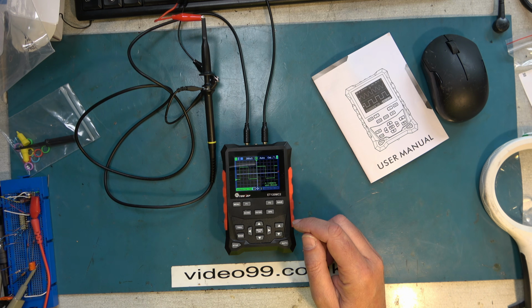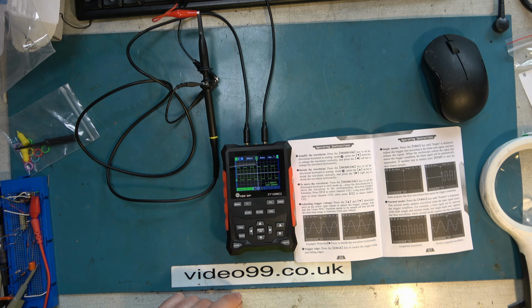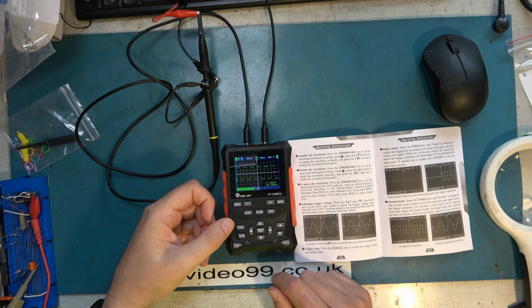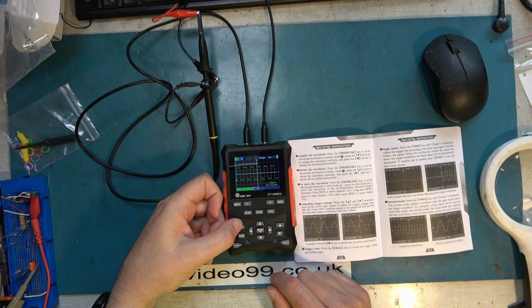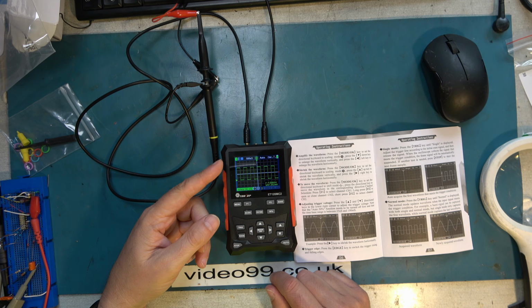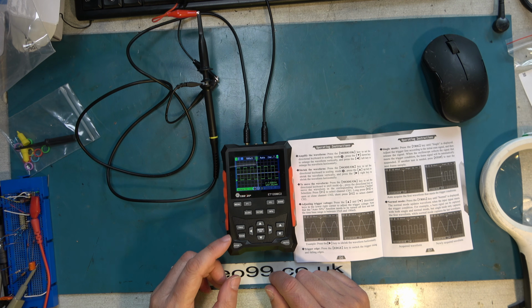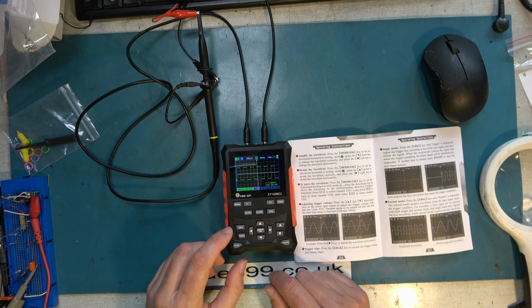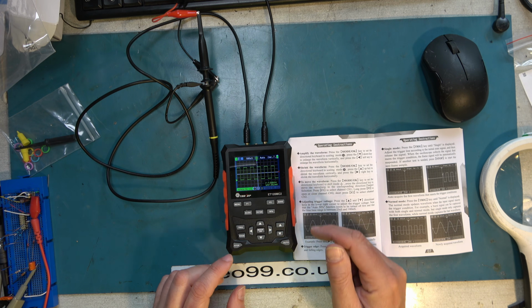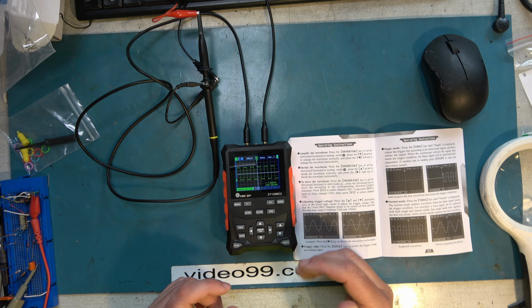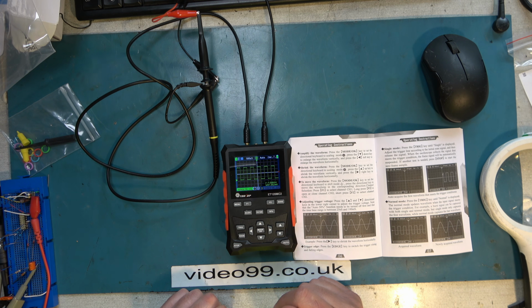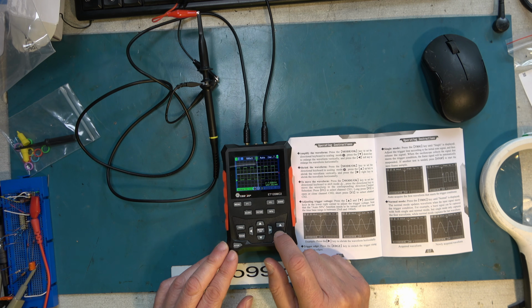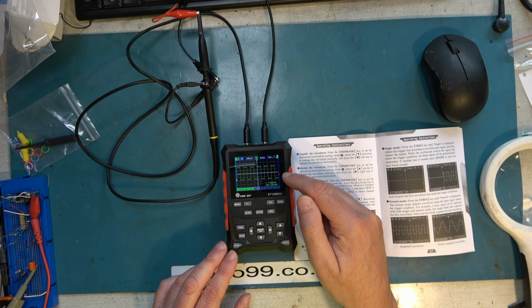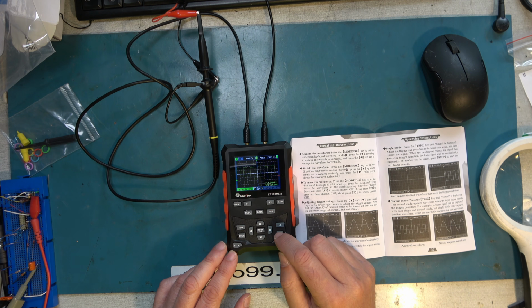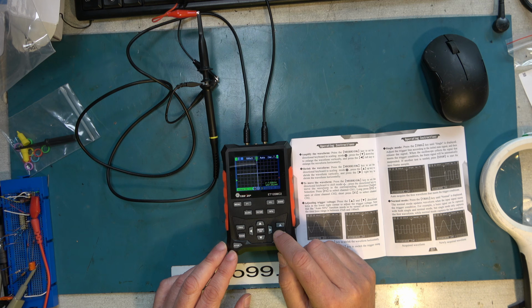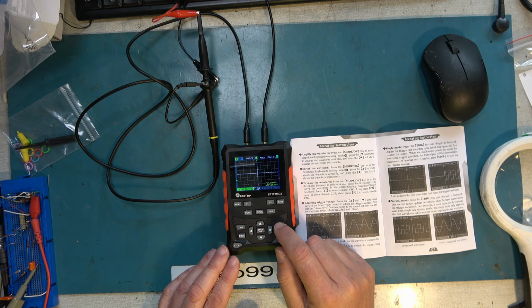How do we adjust it? Let me show you a little bit about triggering. So you can select between single, normal and auto triggering. We'll leave it in auto for a moment, and typically you'll hit 50% to get triggering at 50%, but if you need to trigger somewhere else, then we can use these keys to move the red marker that alters where the trigger is. If we go off, the bottom will become untriggered.